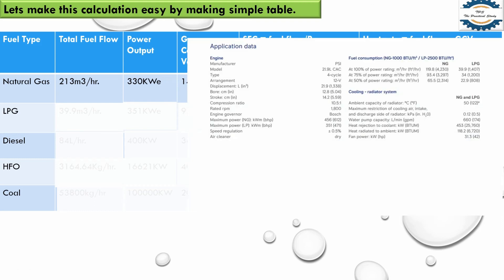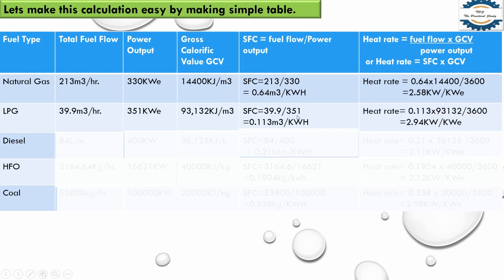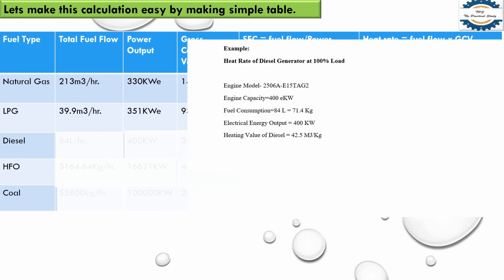For LPG, I have taken an LPG power plant. At 100% power rating, LPG consumption is 39.9 cubic meters per hour and its power output is 351 kilowatt. The GCV of LPG is 93,132 kilojoule per cubic meter. Similarly, for specific fuel consumption we divide fuel flow by power output, and for heat rate we multiply specific fuel consumption by GCV and divide by 3,600.